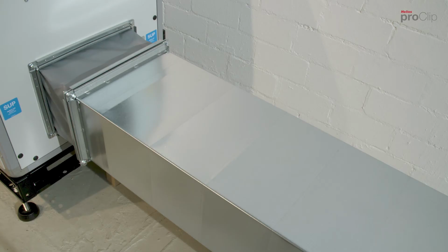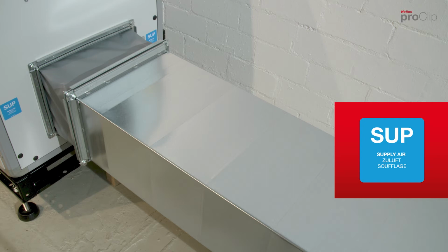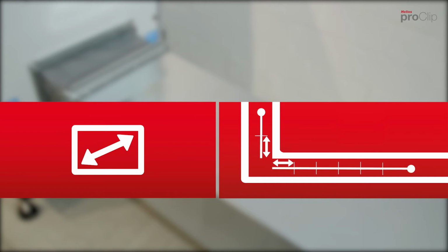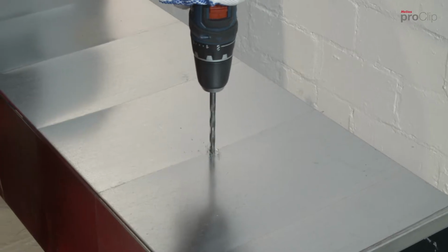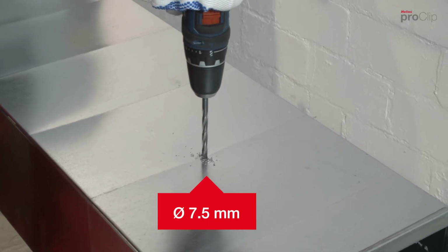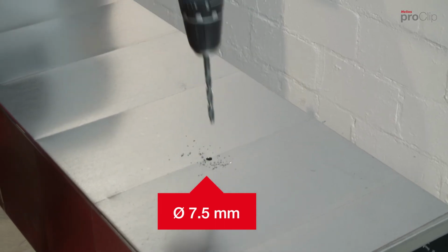The measurement probe is installed in the supply air duct. We recommend 2 duct diameters distance between the unit and bends and forks, as well as 6 duct diameters after bends to avoid a turbulent airflow. Drill a hole in the middle of the ventilation duct with a 7.5 mm drill bit.